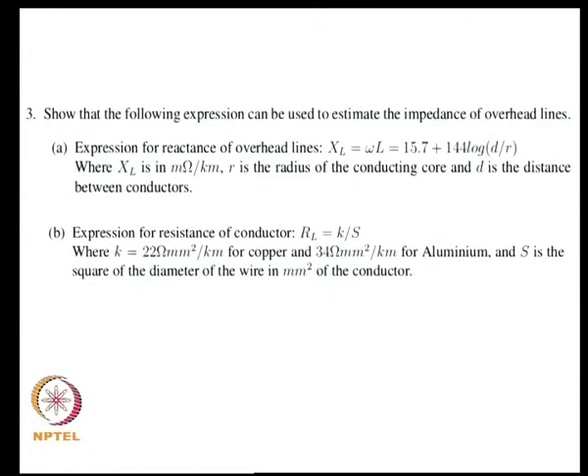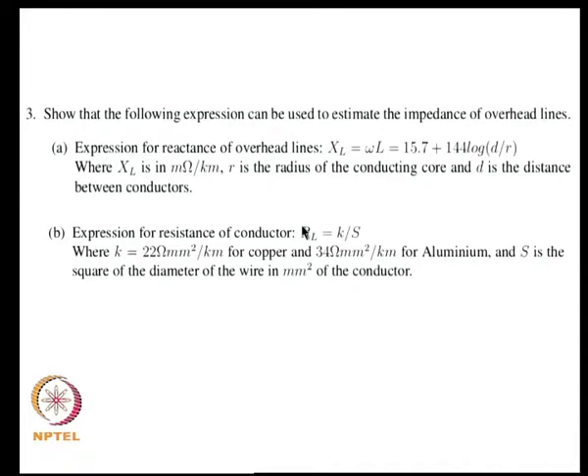In the last class we were working out an expression for the reactance and resistance of the line. We got an expression for the reactance as shown, and the expression for the resistance of the line is determined by the properties of the conductor and cross-sectional area. Once you have the X and R values of the line, you can plot the X/R ratio and get it as some function of the cross-sectional area and the distance between conductors.